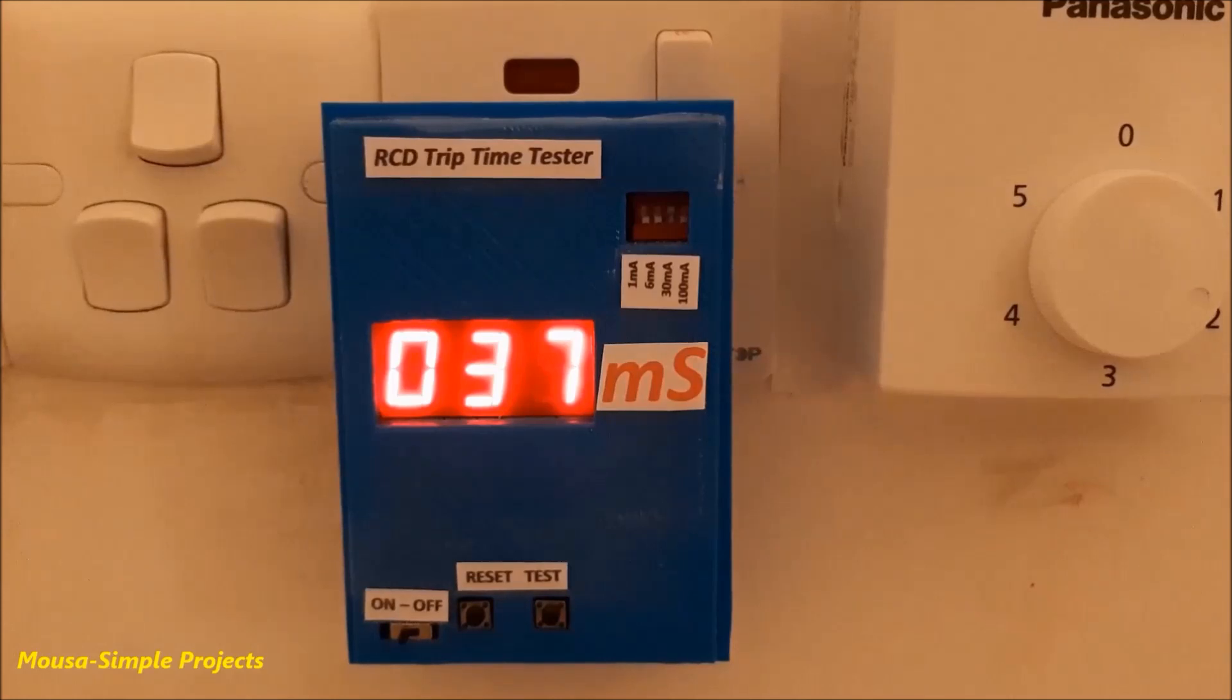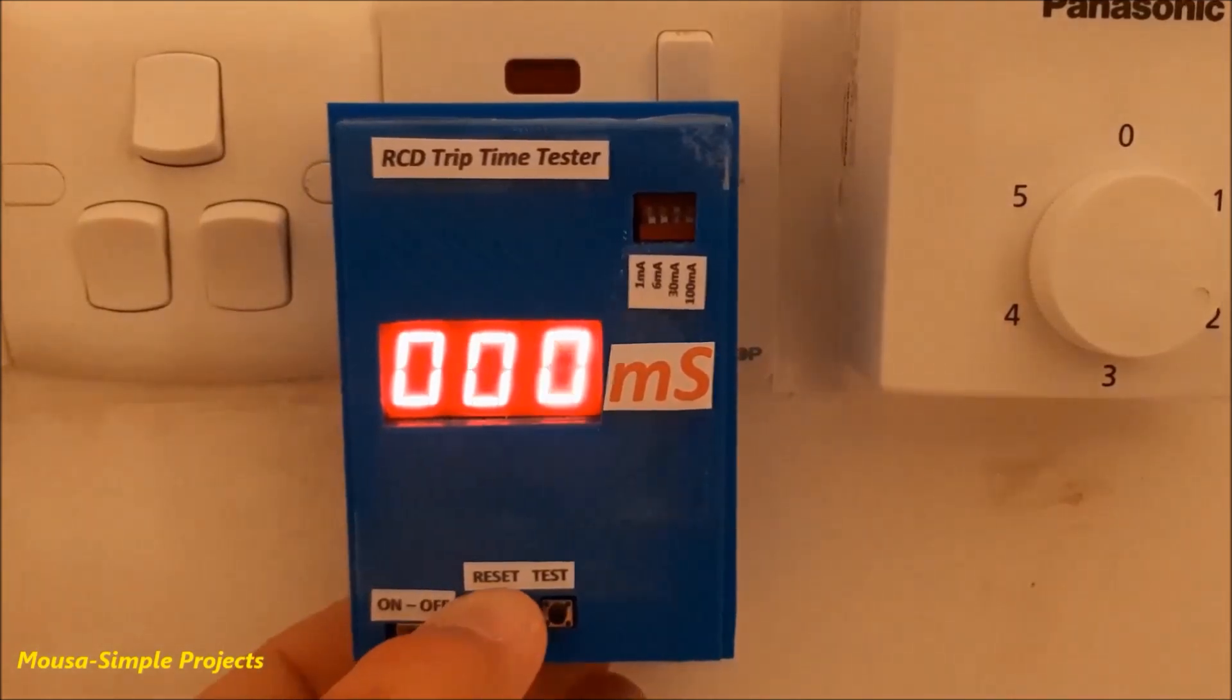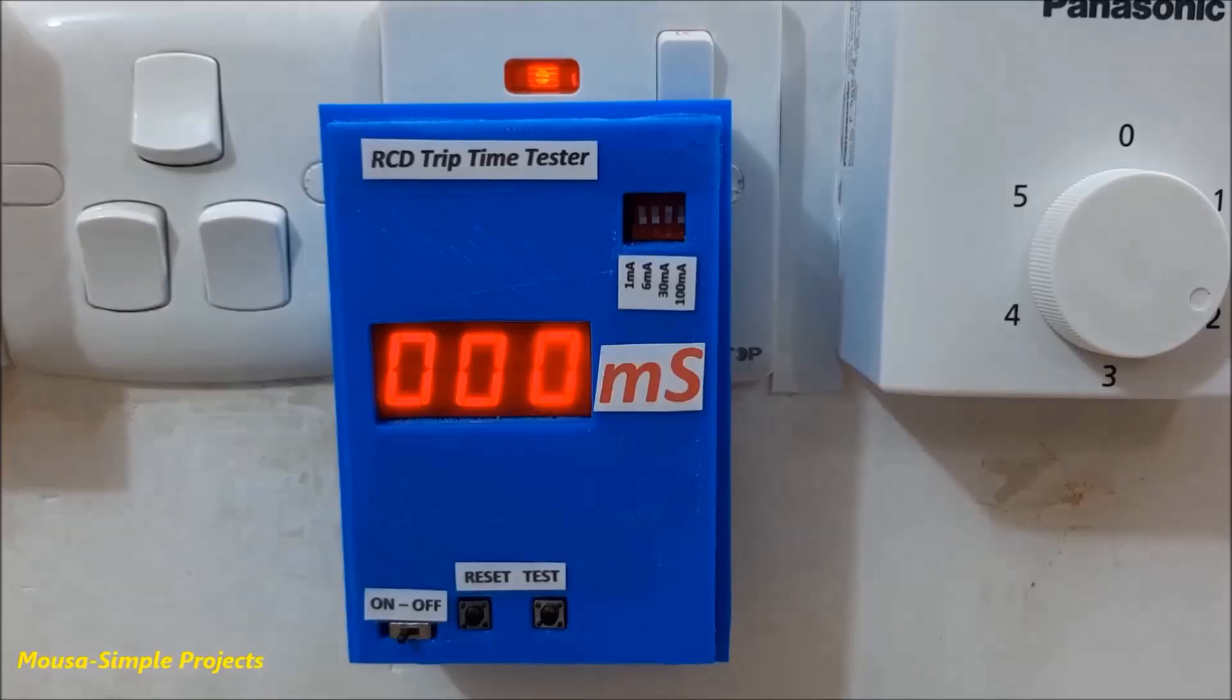As you can see, the trip time in my case is 37 milliseconds. I pressed the reset button and also reset the RCD and tested it again.